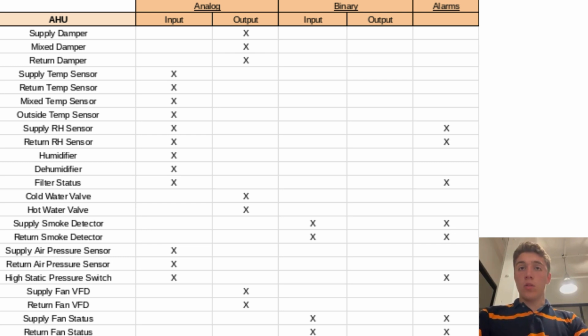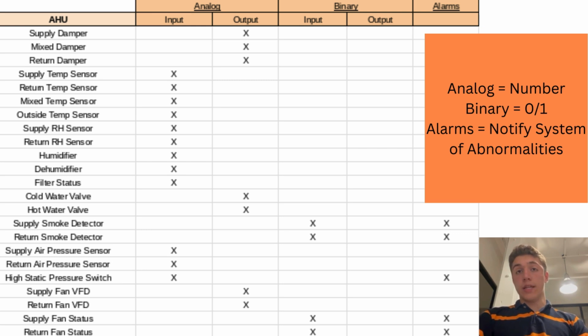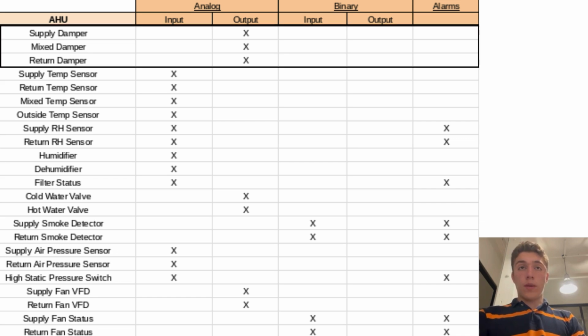So let's take a look at what the points are going to look like. Brief reminder, analog means it's a number, like a temperature, and binary means it's yes or no, 0, 1, true or false, one of two choices. Alarms are going to notify the system if and when something happens by routing to an alarm class and then an alarm recipient. So first, we're going to have the different control dampers, the supply, mix, and return damper, and these are all analog outputs because they're controlled by a motor, which dictates how much they turn.